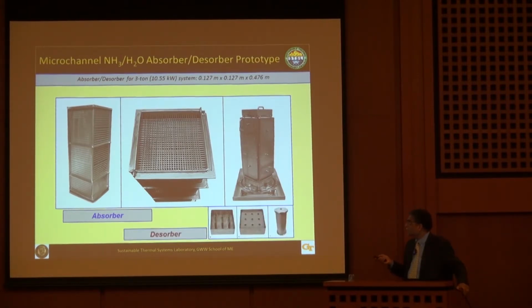Furthermore, while this was an absorber, with a simple change in the distributor tray, we can make this function as a desorber, generating vapor instead. Instead of sending cooling water through the tubes, if we send a heat source, like hot water, through them, it will boil off the refrigerant. So the exact same component can function as an absorber, a desorber, a condenser, or an evaporator.